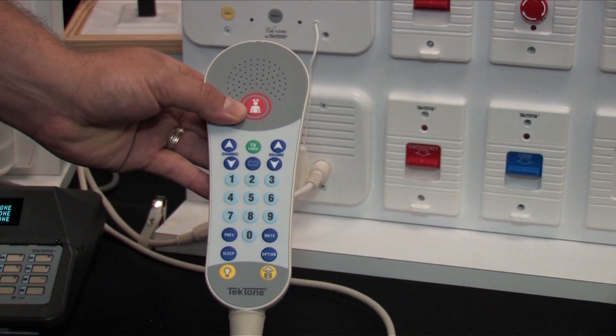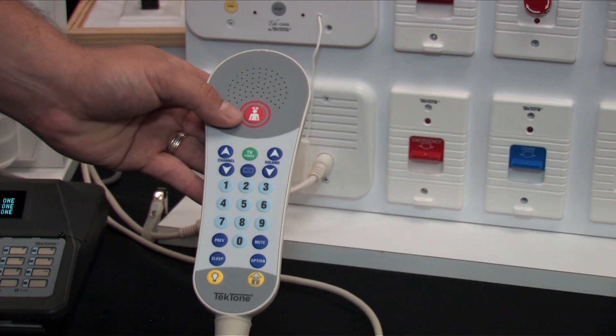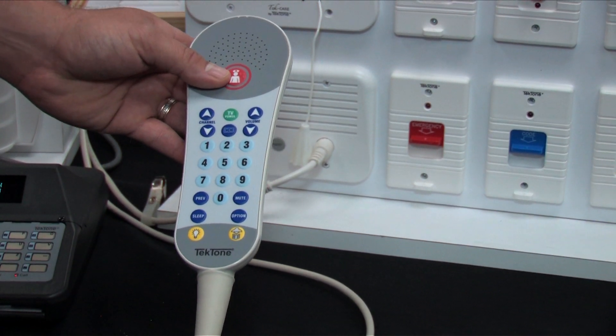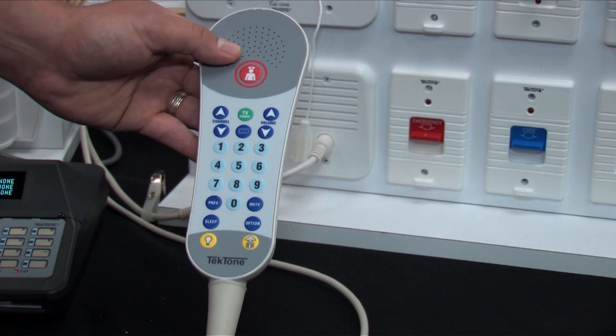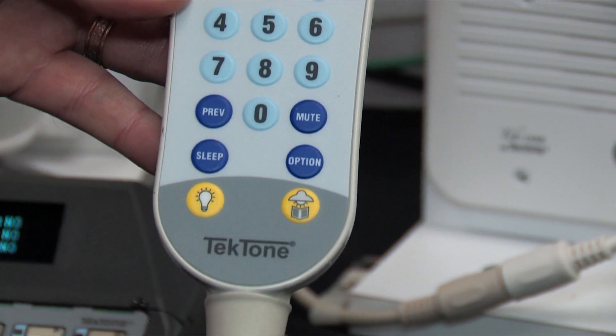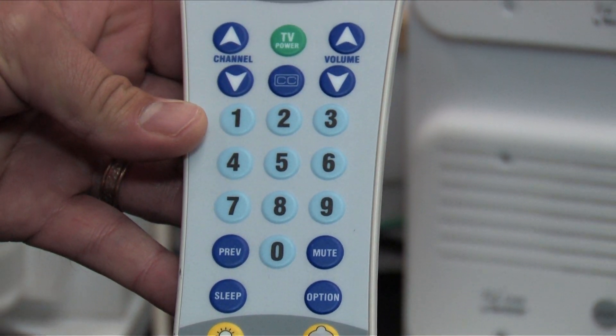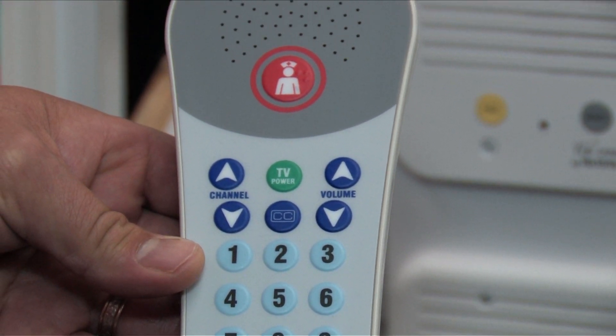This is another feature of the TekTone Tek-Care system. We have pillow speakers that you can use to alert your nurse, and the nurse can actually talk through the speaker back to you. Room lighting can be controlled with this — you have two different lights you can set up. And then also your TV controls are here for controlling your TV.